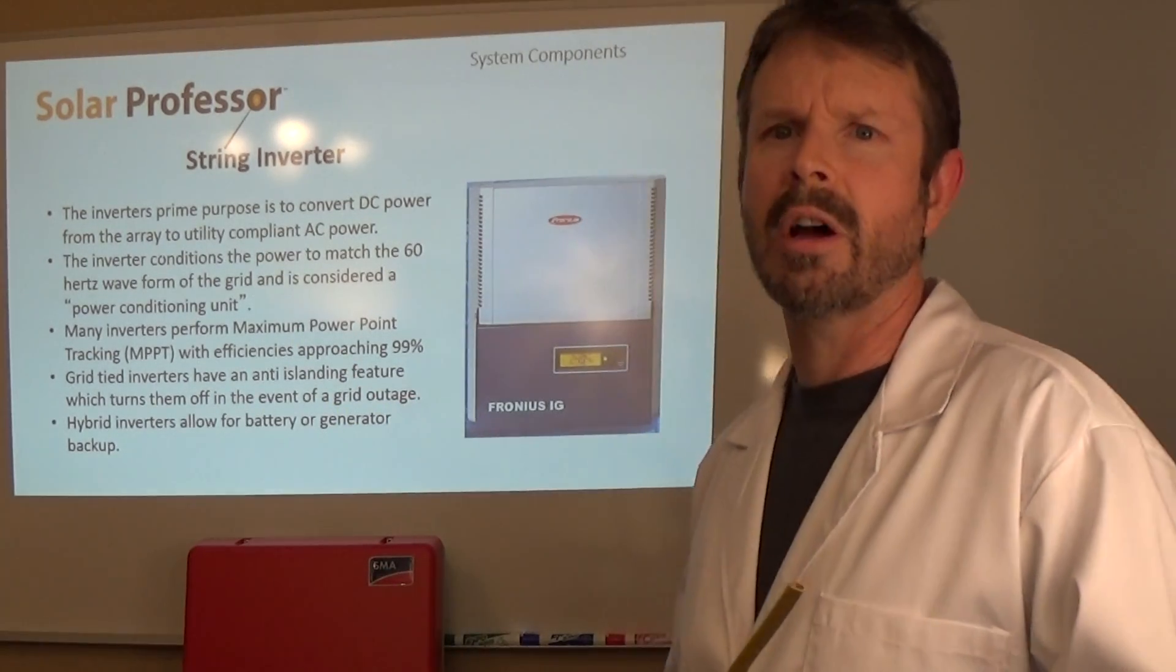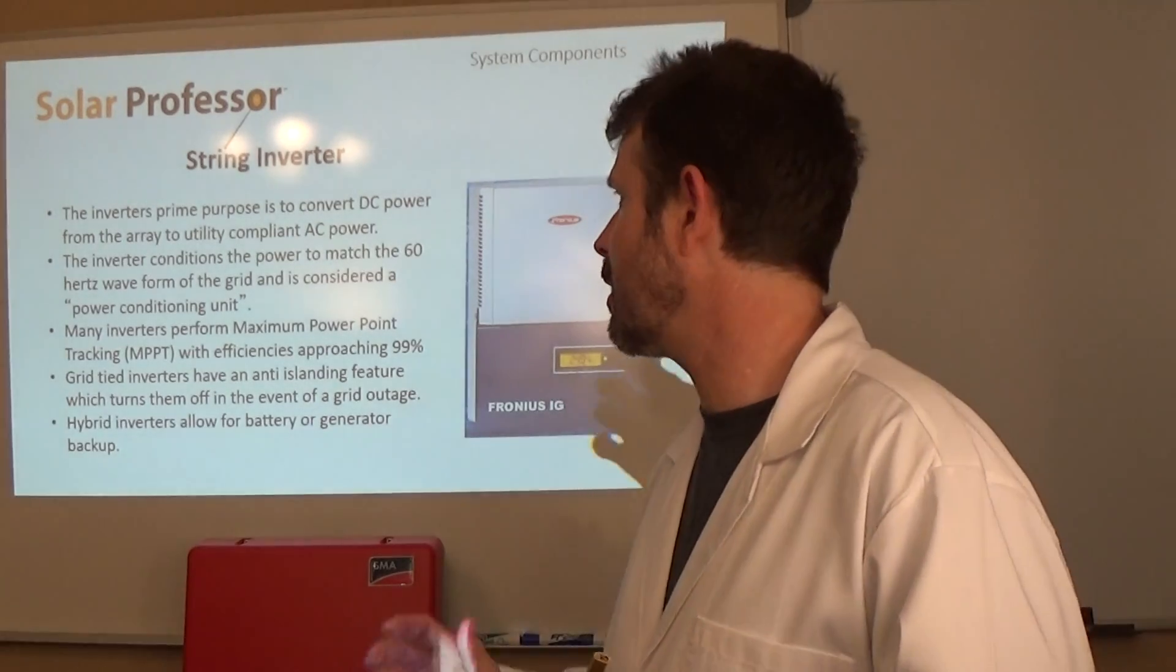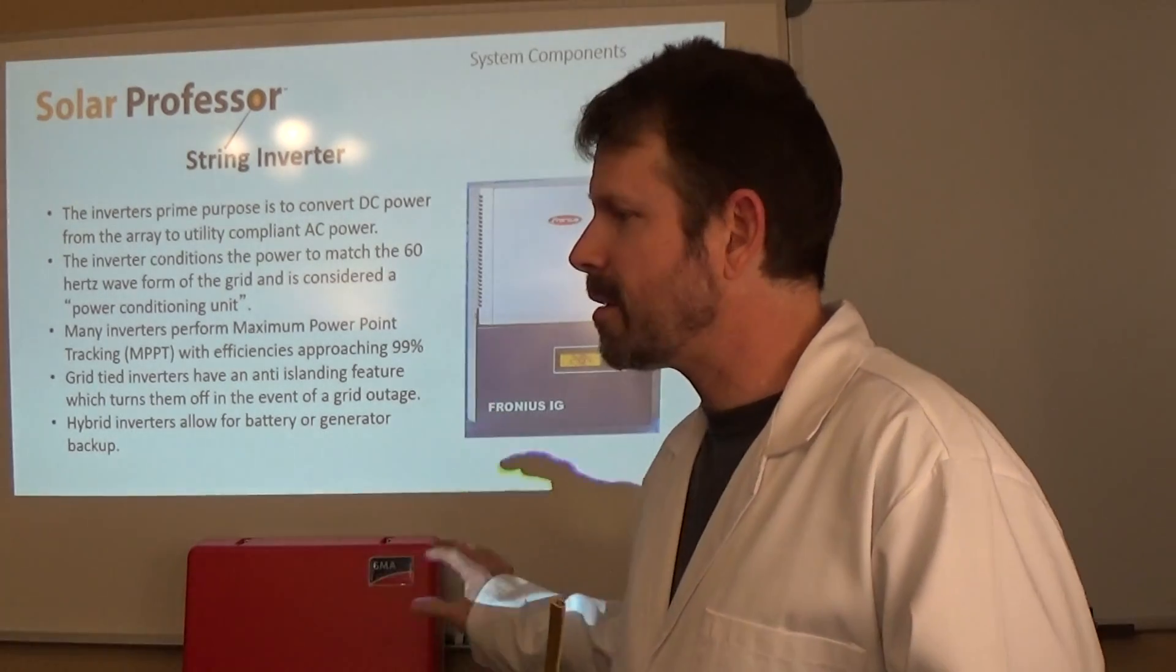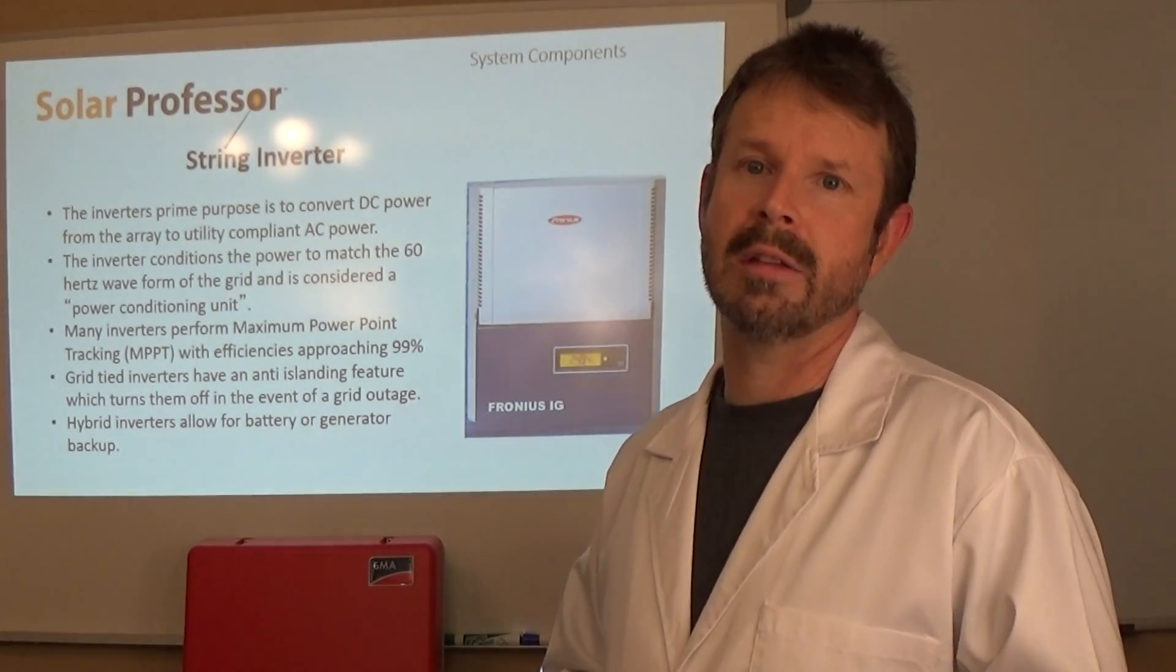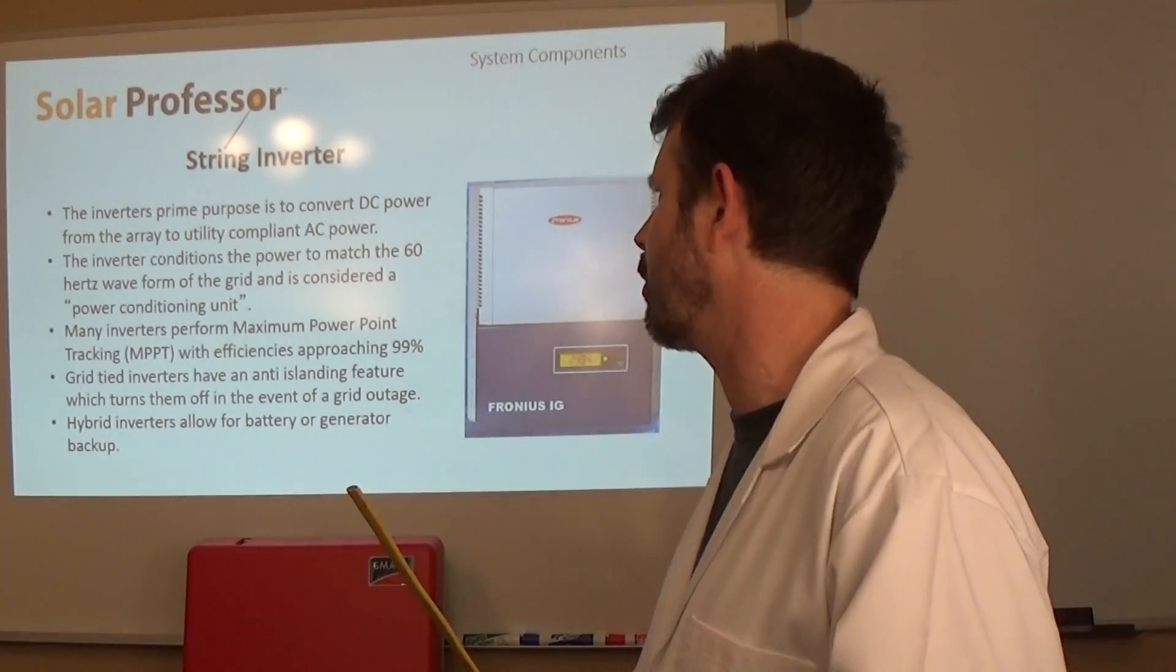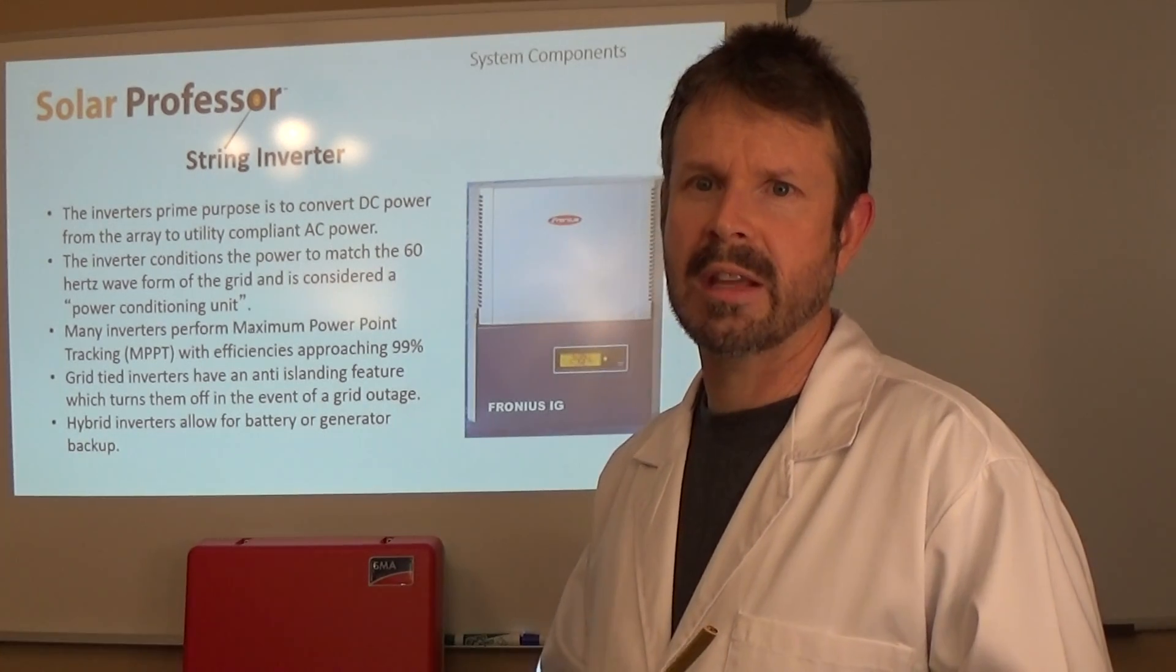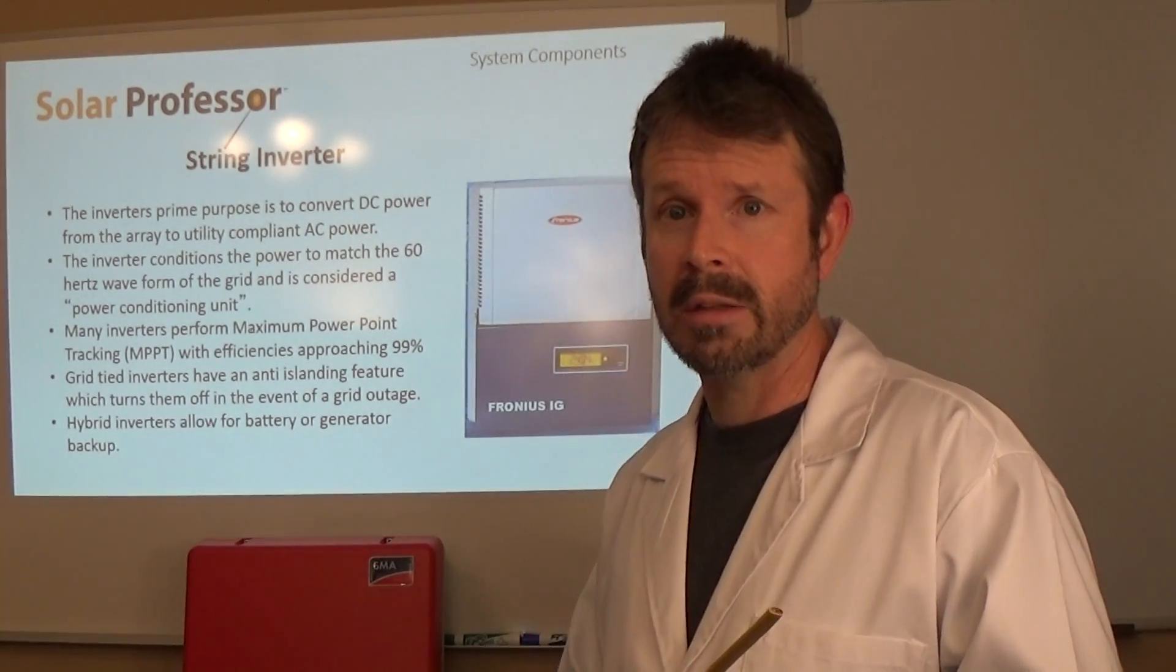Grid tied inverters have an anti islanding feature, which is really important, which turns them off in the event of a grid outage. So one of the big questions in the industry is if the power goes out will my system continue to work and the answer is maybe, it depends on the type of equipment you have. If you have just a standard string inverter like this, no, it's actually going to shut off.